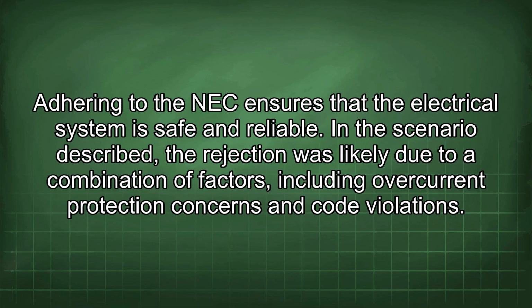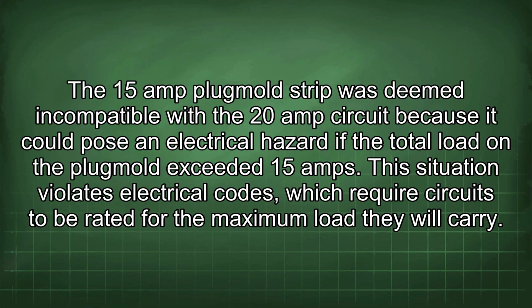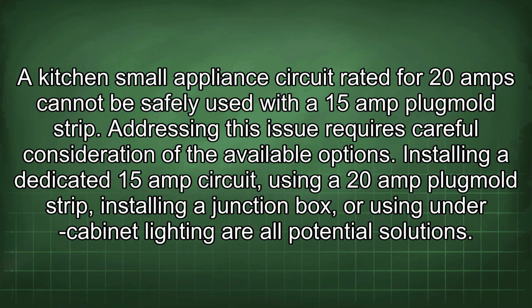In the scenario described, the rejection was likely due to a combination of factors, including overcurrent protection concerns and code violations. The 15-amp Plugmold strip was deemed incompatible with the 20-amp circuit because it could pose an electrical hazard if the total load on the Plugmold exceeded 15 amps. This situation violates electrical codes, which require circuits to be rated for the maximum load they will carry. A kitchen small appliance circuit rated for 20 amps cannot be safely used with a 15-amp Plugmold strip.